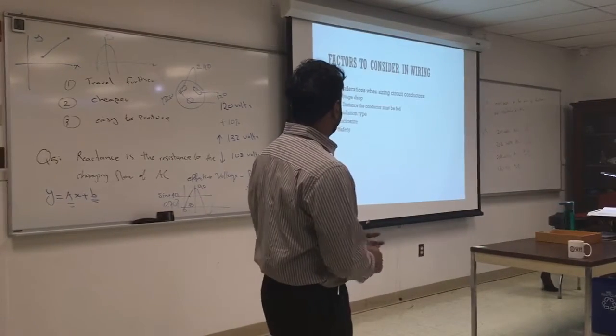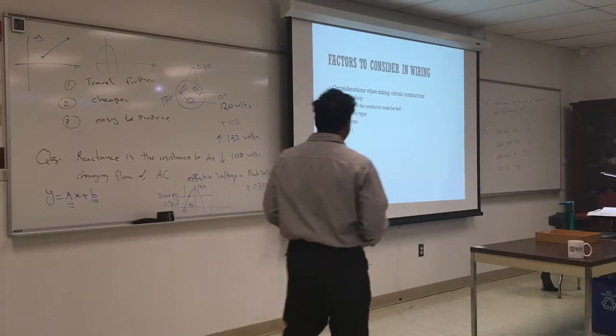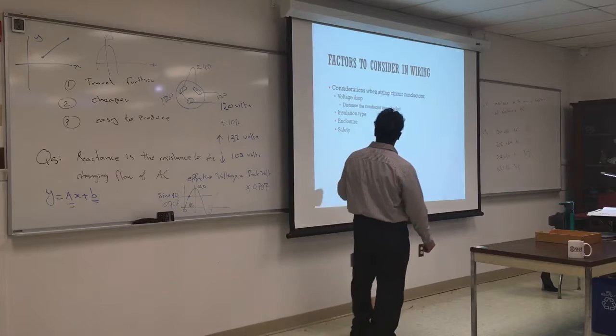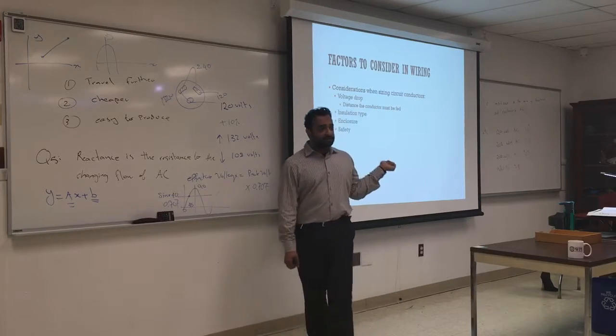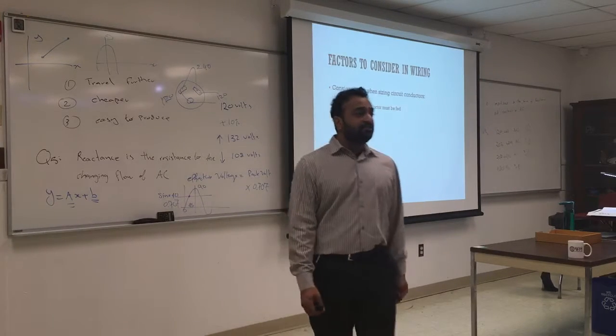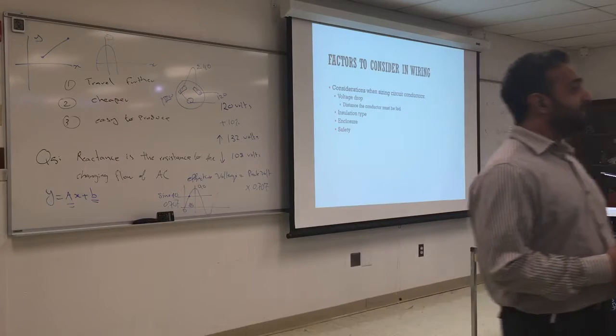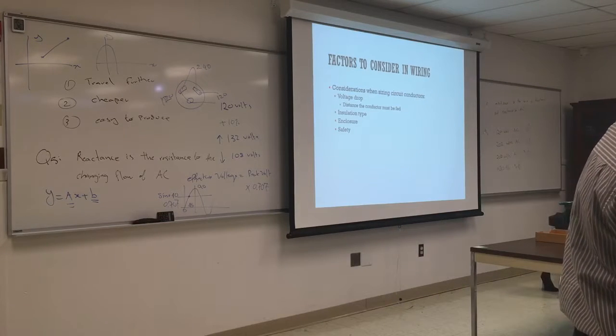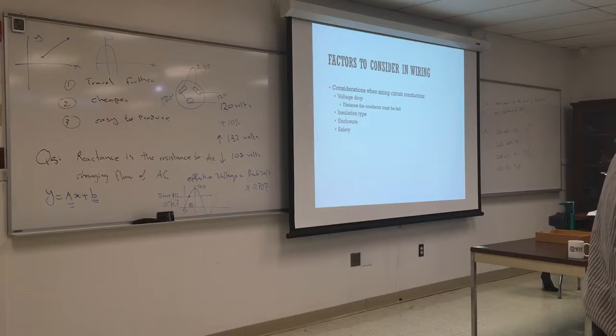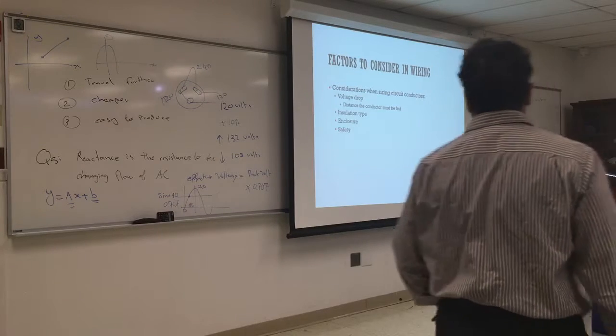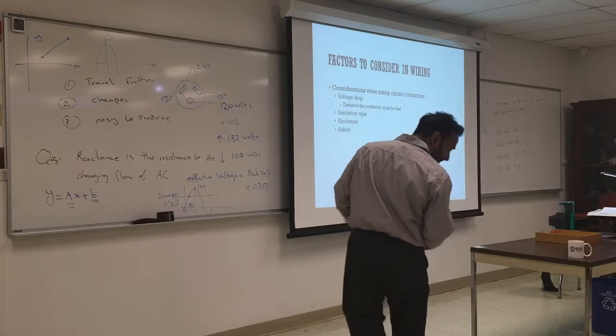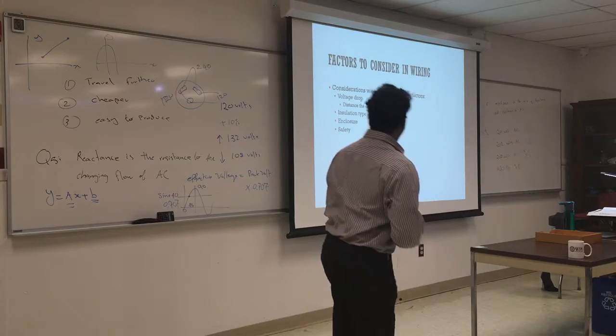So we're still in chapter 8, this is part 2. What are the factors we want to consider when we size wire? It's mostly the voltage drop. Usually check on the equipment, what is the maximum size of wire you can use and how long. If you're going to go longer, probably you have to consult the manufacturer and they might recommend a different kind of wire. So the voltage drop is a big thing when it comes to installation.